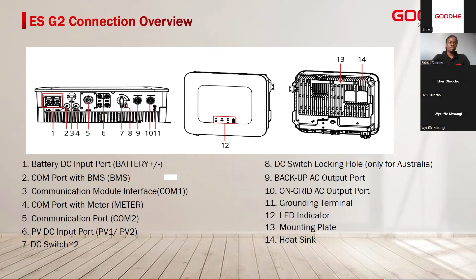In terms of the system diagram, this describes the installation, an SLD of the hybrid residential installation, taking note that we are focusing on the ESG2 and Lynx Home. The ESG2 is a hybrid inverter, as I mentioned before. So you connect the PV strings to the inverter, and you connect the battery power cables and communication cable to the inverter.